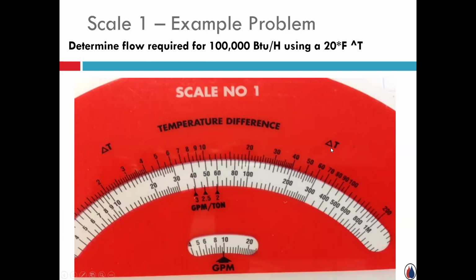So all I've done is taken a screenshot and enlarged scale one. The first thing I want to do is, in that white band that lists the BTUs and MBHs, find 100,000 BTUs, which in this case would be 100 MBH. And I want to line it up opposite the design delta T, in this case 20. So 100 opposite 20. And all you do is look down at the small white window with GPM, and it describes it as 10 gallons a minute. So it's just doing the math: 100,000 BTUs divided by 10,000 is 10.